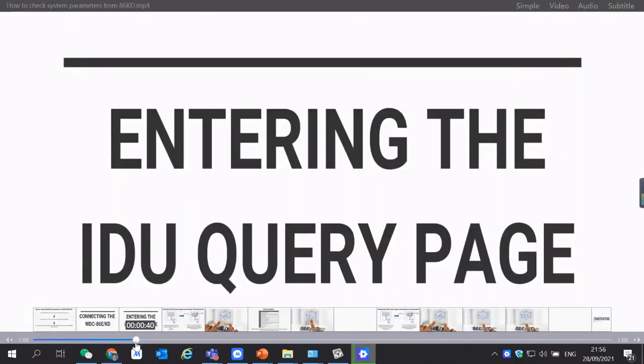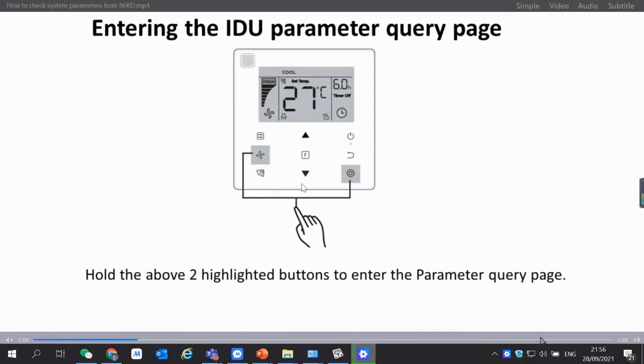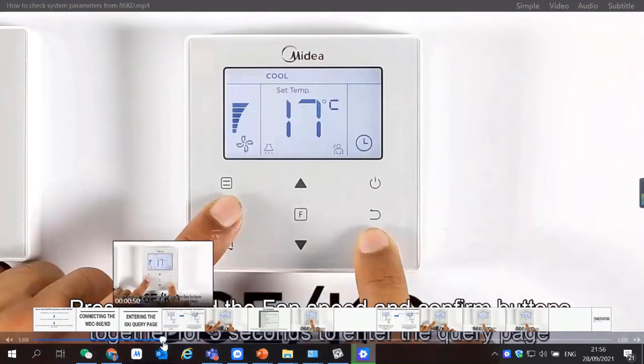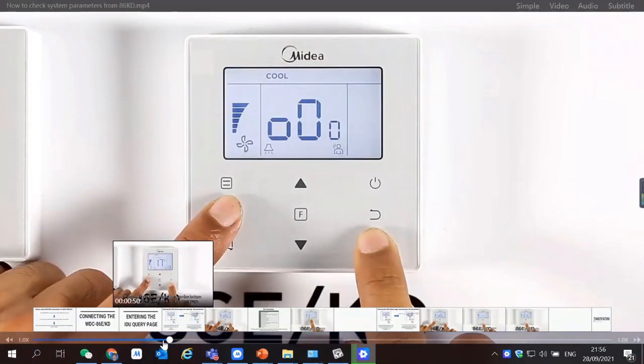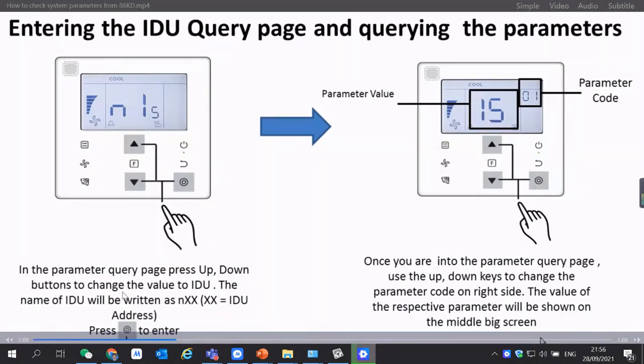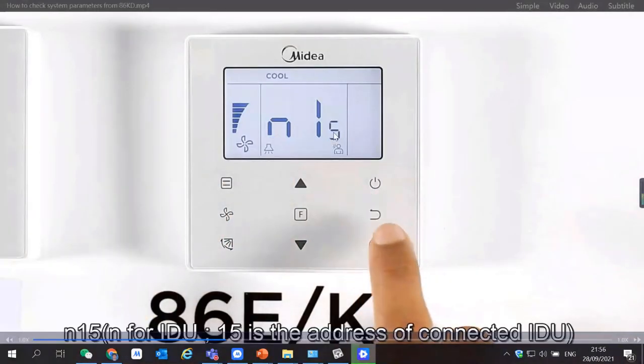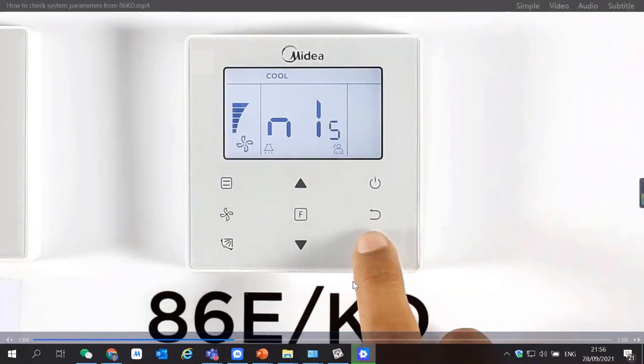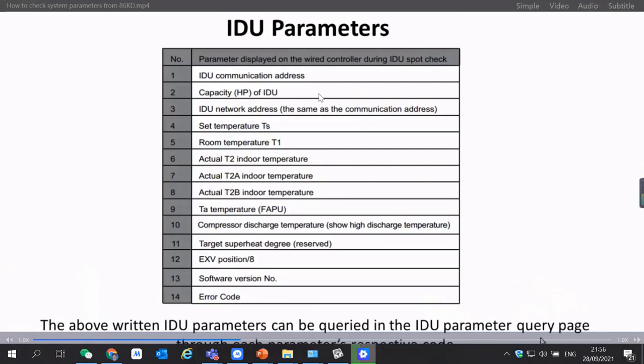So you need to press the fan speed and confirm button together for 5 seconds and then you will enter the parameter query page. Okay, so here we press and then inside the parameter query page, this NXX means the indoor unit. This will be the address of the indoor unit. This indoor unit connected address is 15. Oh, sorry, address 15. It means the only indoor unit that it has connected, right? So here it is N15 and click confirm and then you will see a parameter list. So this is the name of the parameter. Maybe a little back.